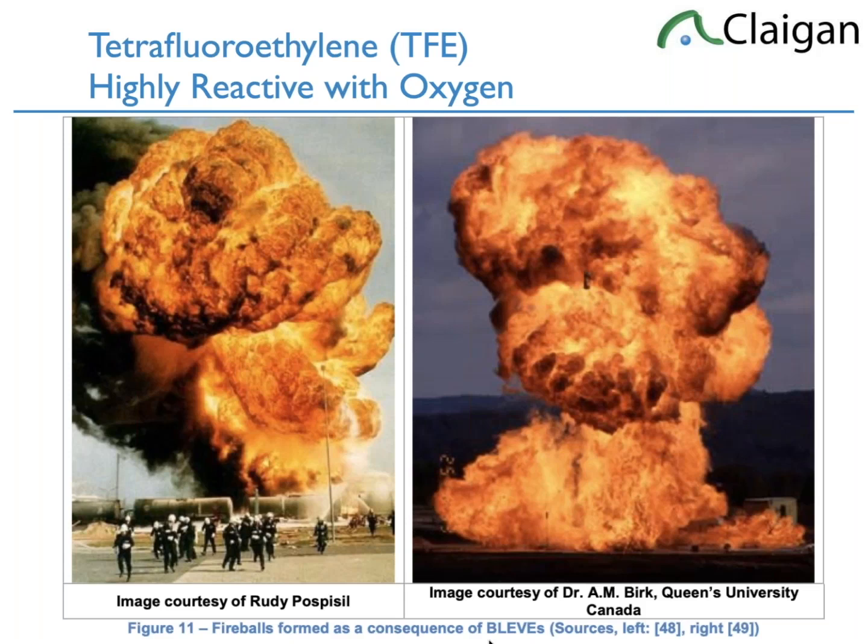So the question is whether or not TFE is above 1,000 ppm. And it is very hard, say, for a lab like us to measure TFE because the control sample is explosive. Fortunately, there's a couple labs that found a way to do it, to keep the TFE from blowing up the lab, which would be dramatic. And they proved that normal PTFE has below detection limits amounts of TFE. It's low risk of being 1,000 ppm, and if it was there, it would react directly with oxygen in the first place and not be a problem. So if TFE was a problem at 1,000 ppm, it would be a big problem in medical devices. Turns out it's nowhere near 1,000 ppm, mostly because of its reactivity with oxygen.